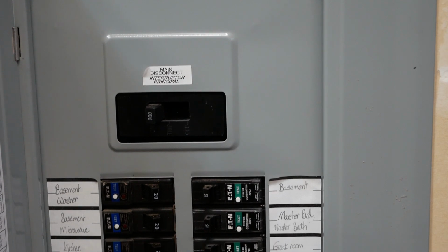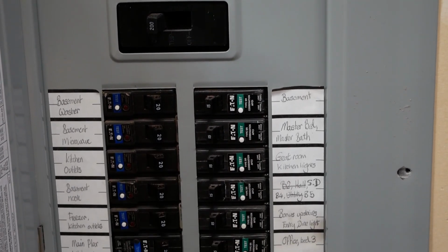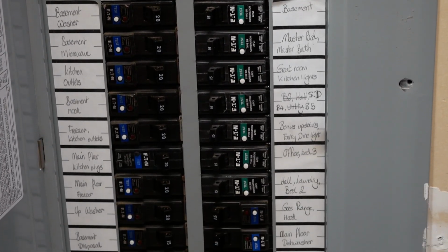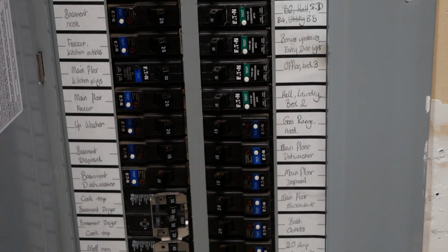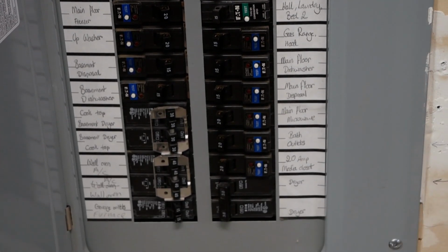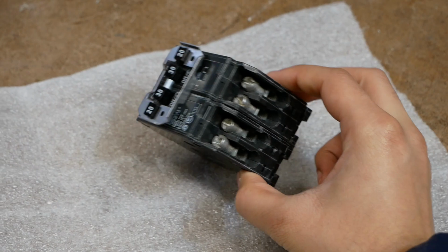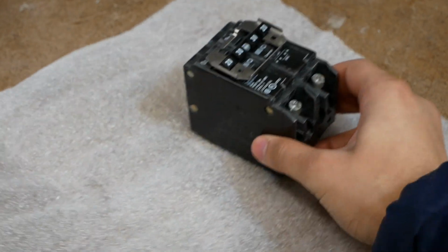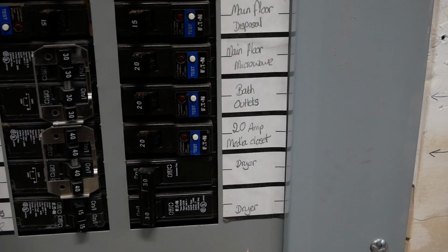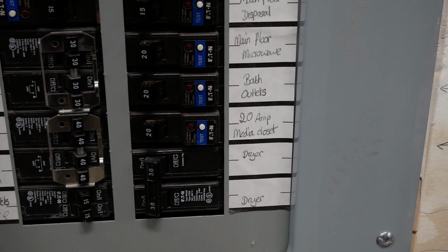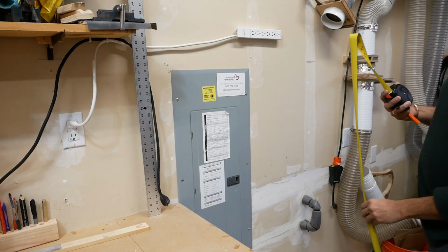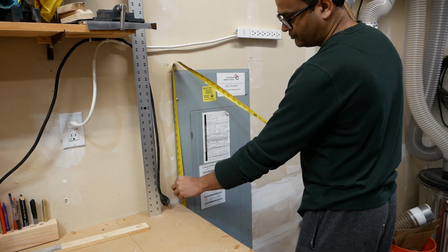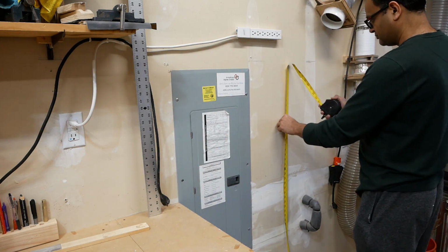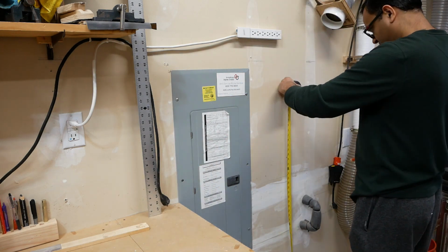Adding a new circuit would have been relatively easy, but in our case there was no space left in the panel. Since we want to add a 240 volt circuit, we need two additional spaces. So the solution we came up with is to replace our existing dryer circuit breaker and use the two existing spaces with a combination, or quad, circuit breaker that provides 30 amp and, in our case, an additional 20 amp circuit. So this is what we are going to do today.